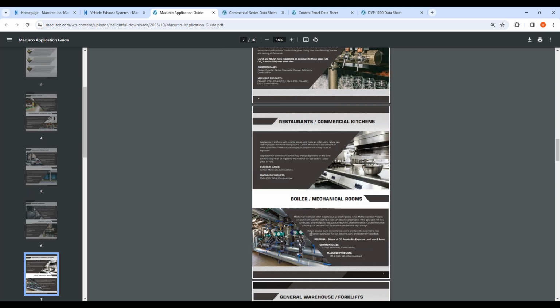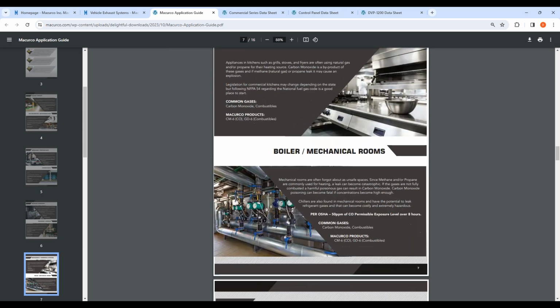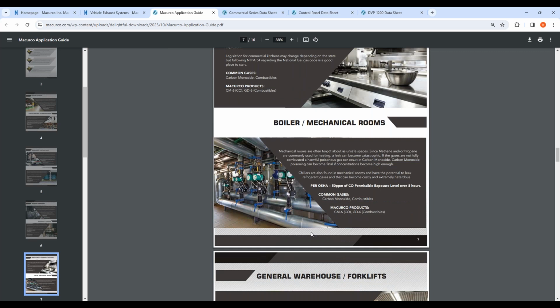The big one is the boiler mechanical rooms. This is pretty much the hottest ticket we have right now in terms of all of our applications. It started in the state of Texas about 3 years ago, and it's manifested itself to about 15 other states throughout the country. Almost every state is starting to implement something like this. And what it says is basically all boiler rooms that have a boiler or a furnace that's 200,000 BTUs or more have to have a CO shutdown system.